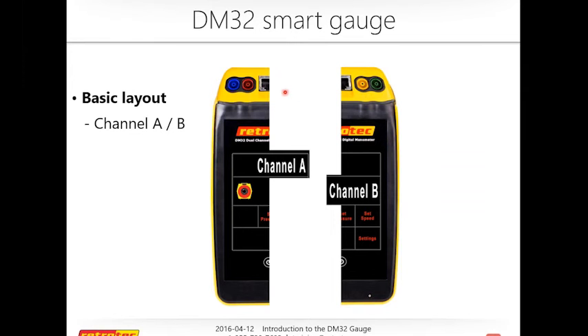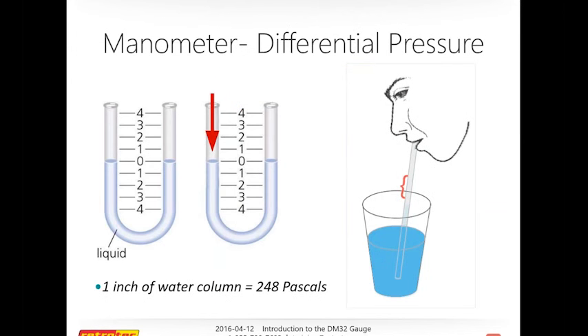Before we go further, I want to talk about what a manometer is. It's a differential pressure gauge, so it measures the pressure difference between two locations. That's important to understand, because I frequently talk to people who are very savvy and have been running tests for a long time, but never really grasped that the results they're given are just the difference between two points. That's comparing an input location to a reference location, but it's not an absolute pressure.